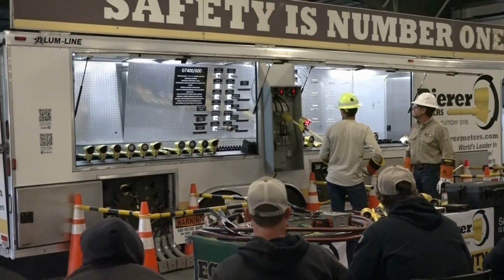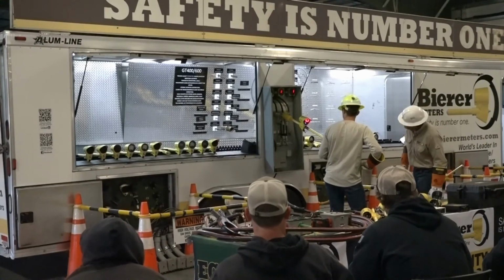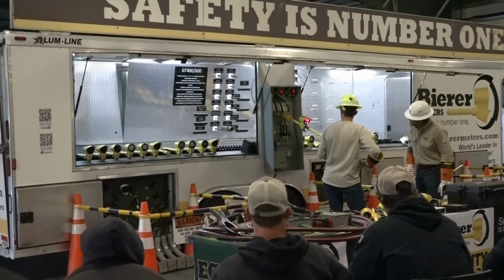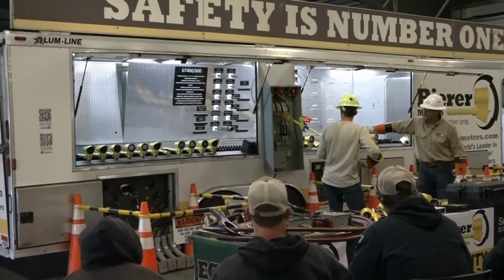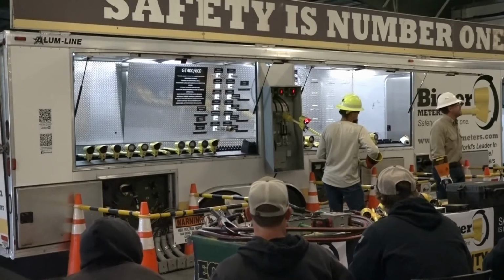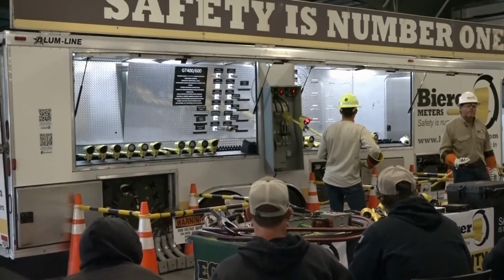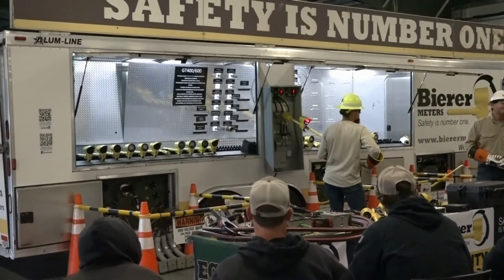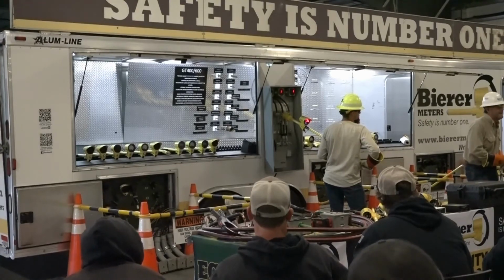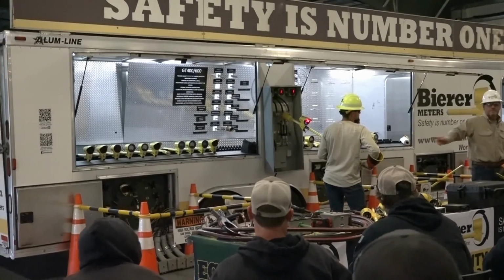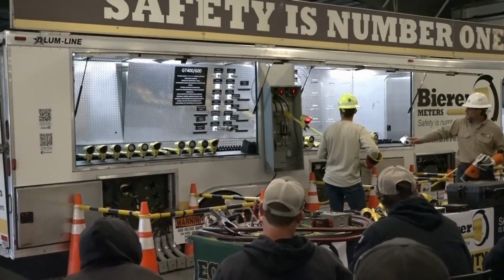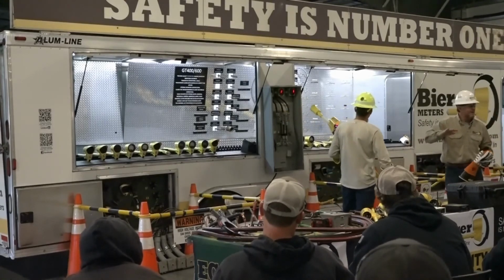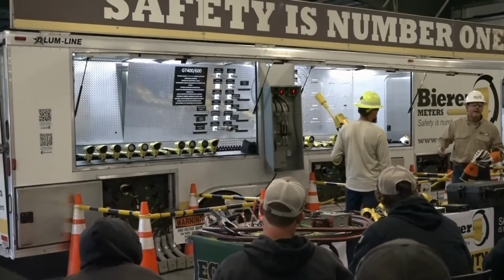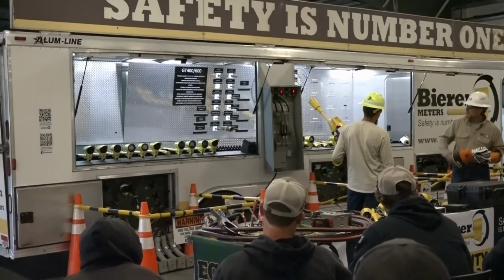Close to it, all right, we got a blue light. See that yellow light blinking? If you see a yellow light blinking, it's telling you you're 30 degrees or 20 degrees or more out of phase. That's going to be an indication you're out of delta Y transformation, that tool's designed to do that. Here it's just telling us that generator's not very accurate, but it's a blue light, we know that's a B phase. Okay, go to the last one.